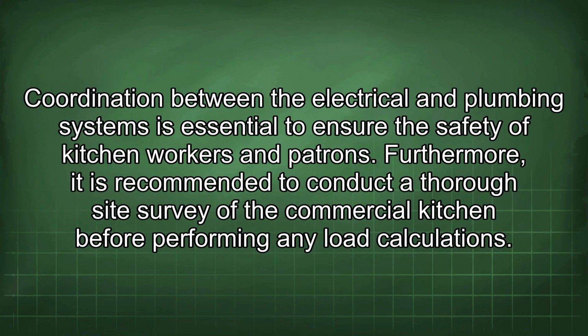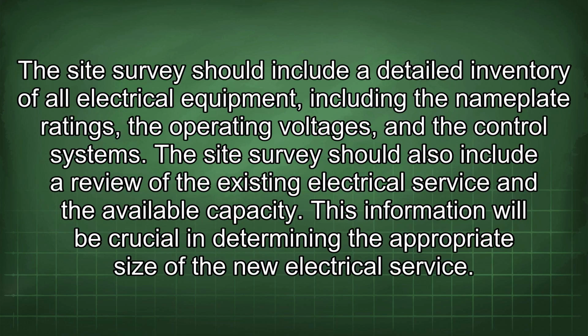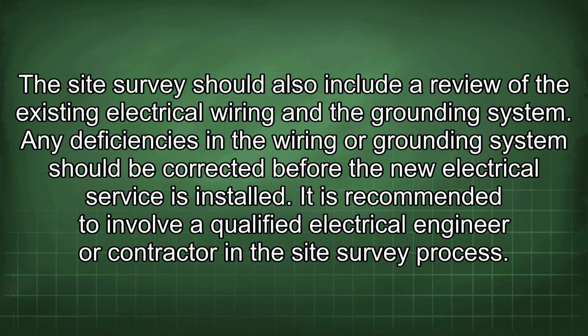Furthermore, it is recommended to conduct a thorough site survey of the commercial kitchen before performing any load calculations. The site survey should include a detailed inventory of all electrical equipment, including the nameplate ratings, the operating voltages, and the control systems. The site survey should also include a review of the existing electrical service and the available capacity. This information will be crucial in determining the appropriate size of the new electrical service. The site survey should also include a review of the existing electrical wiring and the grounding system. Any deficiencies in the wiring or grounding system should be corrected before the new electrical service is installed.